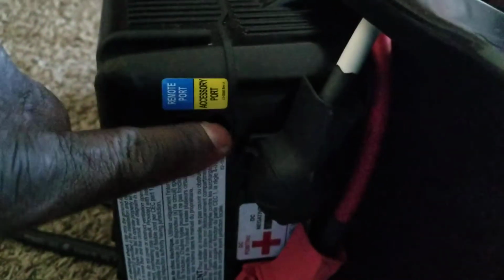So to do that, temperature sensor - but we don't need a battery temperature sensor because these are lithium-ion batteries, they have a battery temperature sensor built in. Disconnect them because you're going to have trouble charging. You don't need a battery temperature sensor on the lithium batteries unless you want to, but it's going to restrict the charge. Anytime it senses that temperature, it's going to restrict the inverter. Or if you want to use a temperature sensor on the kit, it has a temperature sensor you can hook up to the battery or drop it inside the battery box. It senses the temperature in there and slows down the rapid charge into the batteries.